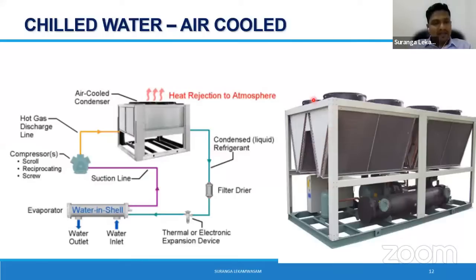Okay, you can find chill water systems in the industry. The first one I want to touch on is the air-cooled chill water system, not common in Sri Lanka, but you can find many, or 99%, of installations in the Middle East, because they don't have water. Instead, they have oil. So energy is not a problem for them. Efficiency is not a matter. So air-cooled chillers are very popular there, but not here, because we have an issue with energy, but we can tolerate the water availability.